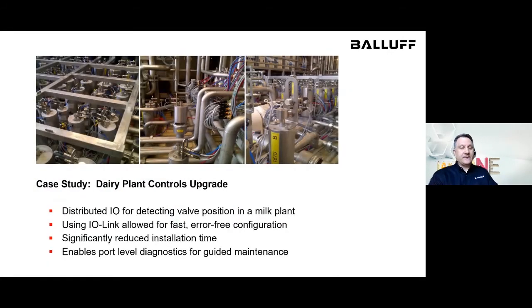What's also exciting about IO-Link from the smart factory perspective is the ability to easily retrofit and upgrade your existing system to get enhanced troubleshooting and diagnostics. You can distribute your IO, detect different positions of valves, and troubleshoot more easily because you're dealing with port level diagnostics right to a device rather than fishing through wiring, giving better guidance for maintenance.